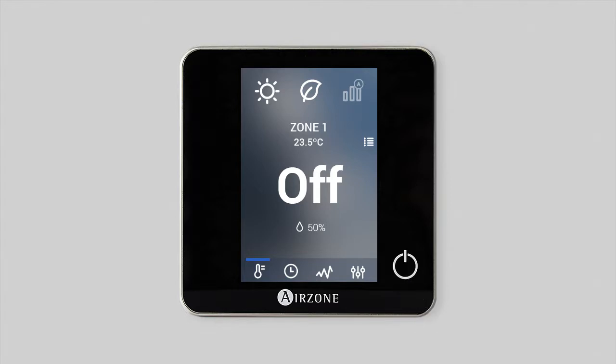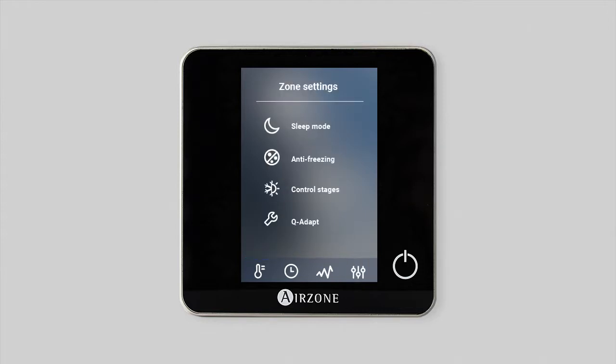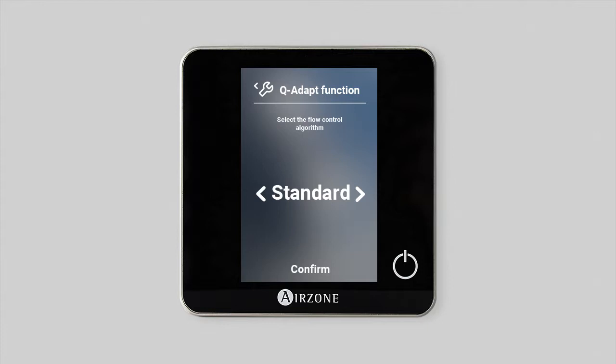This function is configured from the zone setting menu on the blue face thermostat. It offers five options to choose from. Standard: this is the default factory setting. Select the ventilation speed to maintain balance between the airflow supply and the sound level in the zone, depending on the number of zones on demand.